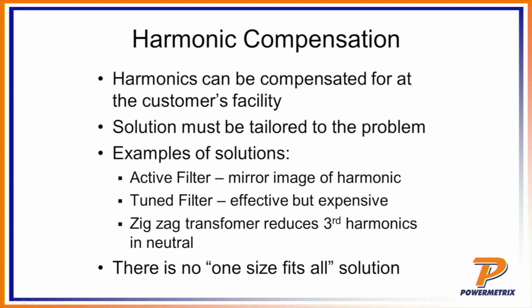Some examples of solutions that are out there, first of all, would be an active filter. An active filter is going to be a system that's going to actually go out and measure the harmonics and generate a mirror image. It's basically counter opposing that. Those of you that use noise reducing headsets use the same principle. The headset measures the outside noise, say there's a vacuum cleaner running. It analyzes the harmonic, and then it injects that waveform into your ears, which is a mirror of that waveform, in effect canceling it out. The active filter for an active harmonic system will actually do that.